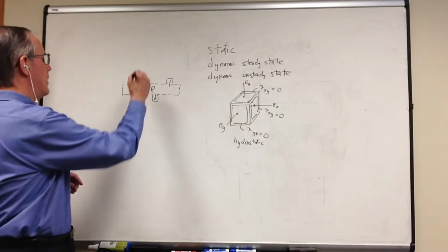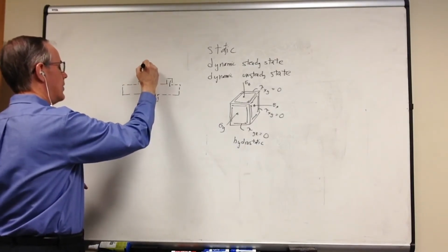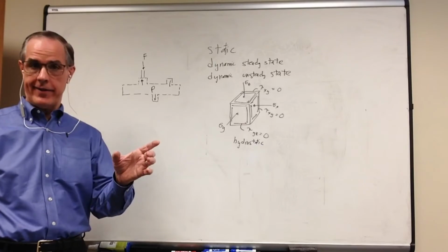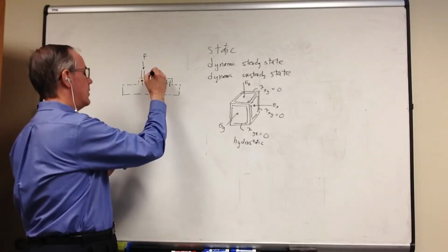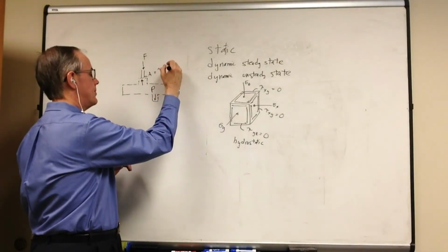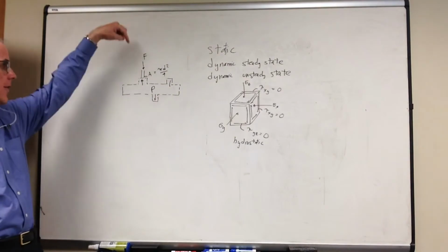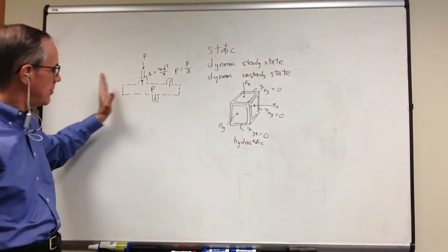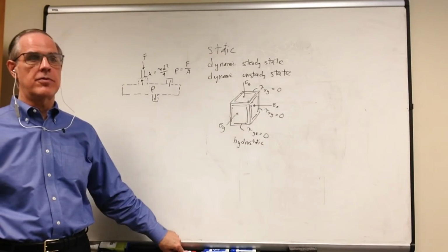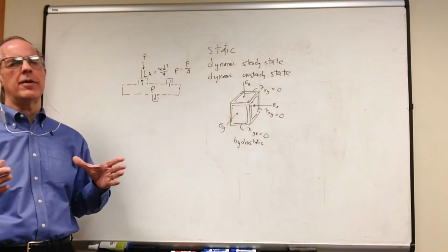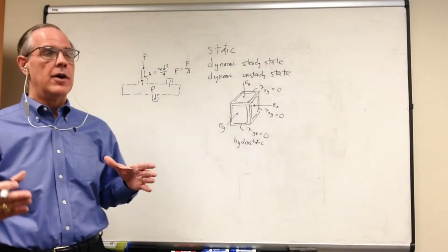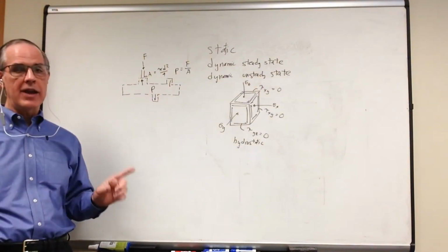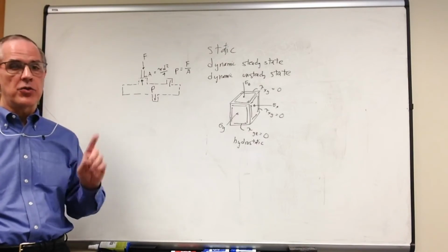If I, for example, apply a force at one point, with this dead weight pressure gauge tester, we apply a force using gravity to an area, which is right here, the diameter of that little plunger squared over four, and that produces a pressure which is equal to force over area. That pressure is communicated throughout the entire internal of the structure, or in this case, the fluid cavity. Excuse me, I've spent too much time in structures. The entire fluid cavity has one pressure, and that pressure can be read by one gauge, or in our case, at least to start with, 3 gauges.